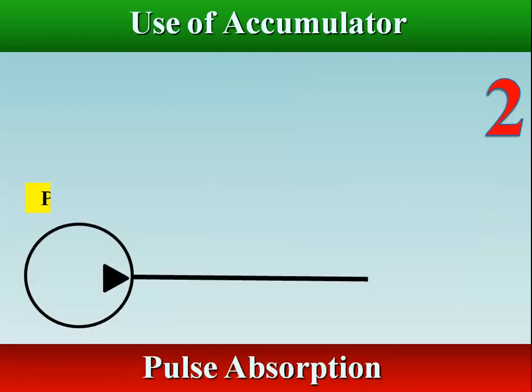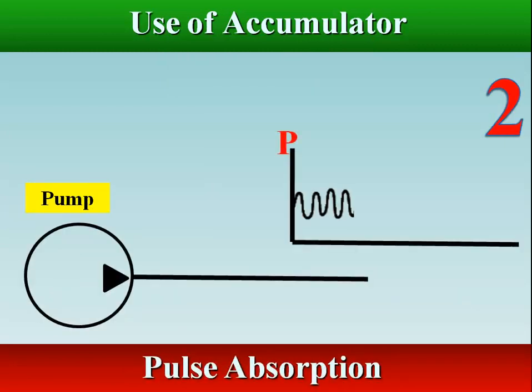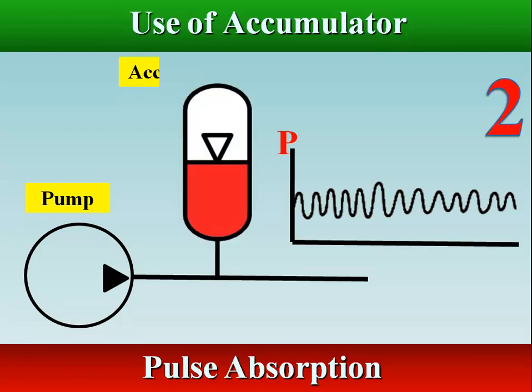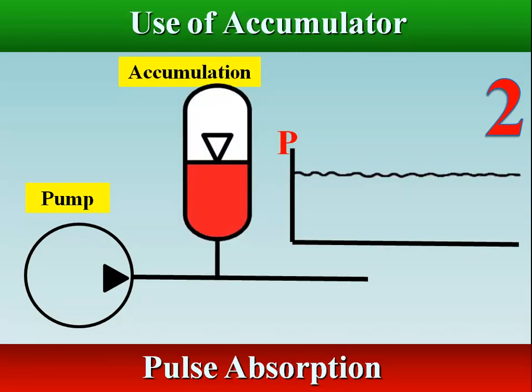All pressurized fluid discharged from pumps has a pulse. Pulses produce noise or vibrations that can cause instability or damage devices. The use of an accumulator can attenuate pulses.